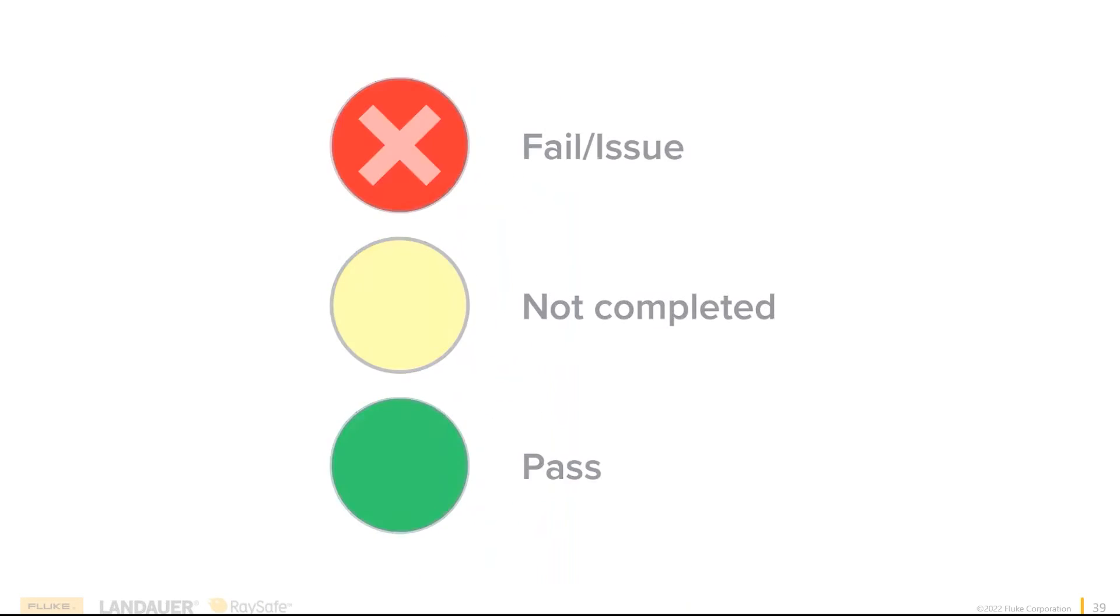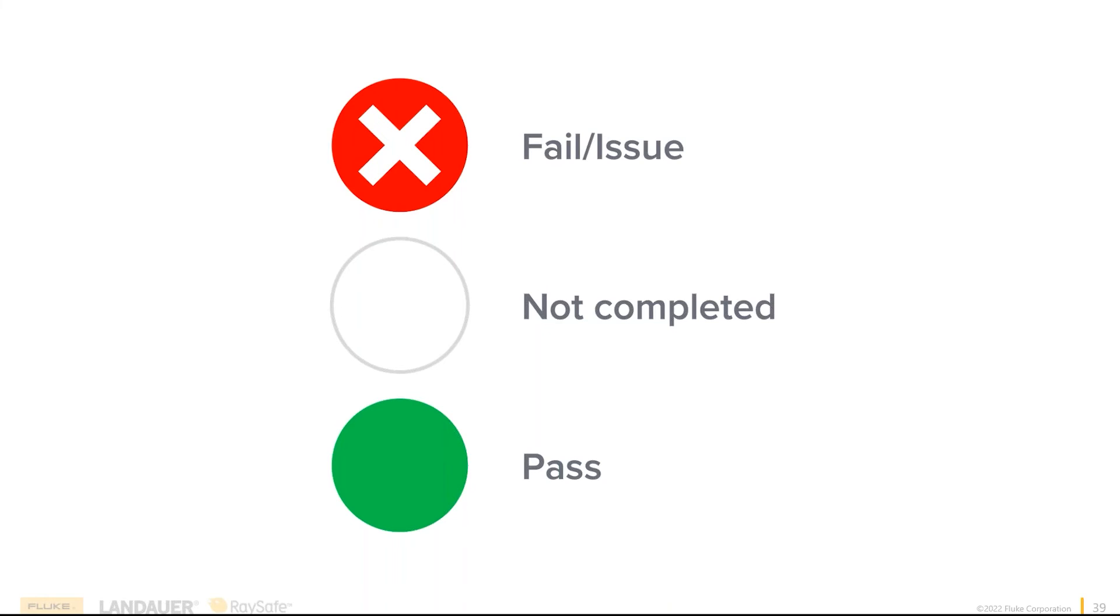There's a lot of things here. Let's just take a break. Red light. Why do we have a stoplight? As children, we all played red light, green light. OneQA is built much the same way. Anytime you complete a step of your procedure and it passes, you get a green light. Green is go. Move on to the next step. If you have a failure, you have an issue, something's out of tolerance, you get a big red circle with a white X in it. Stop. Failure. Issue. You can either then annotate the issue and open up a repair work order, or maybe you want to facilitate the repair right now and retest that parameter, in which case you get your green light and you move on. So green is go, red is stop. That leaves the yellow light, but actually we just used white. White means not complete.